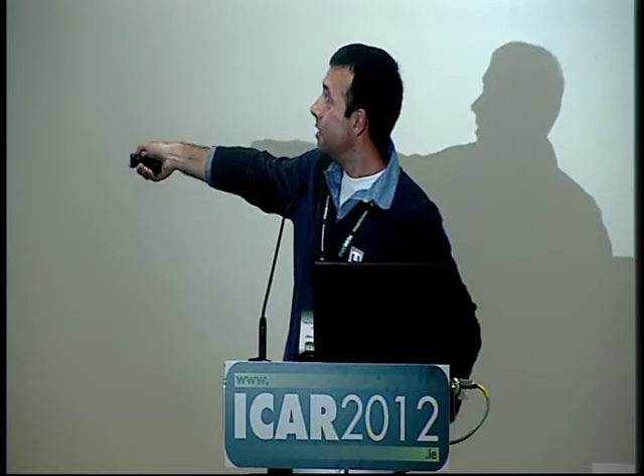Here I have my master, and here I have my slave. I take a certain wavelength for my master, and I try to correlate this information with a window around that wavelength in the slave instrument. And this is done just by a classical linear regression model.